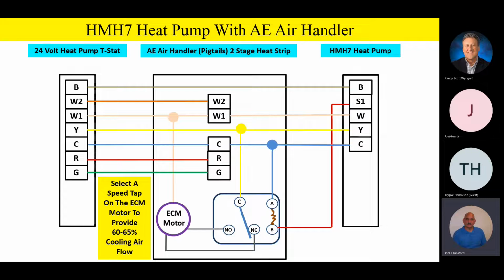So when we call for reduced airflow, because remember the HMH7 heat pump is a five-stage modulating heat pump, what it does is it actually modulates, and when it hits a certain point of modulation, it's going to generate an S1 call. And what it will do, it'll switch that relay and call for reduced airflow.